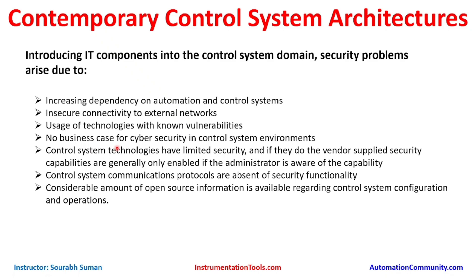There is no business case for cyber security in control systems because there is no tangible return on investment. Control system technologies have limited security, and vendor-supplied security capabilities are generally only enabled if the IT administrator is aware of them. Additionally, adding third-party security can void the warranty and support from vendors, so security technologies need to be tested and released by the OEMs before they can be considered well-tested and implemented.